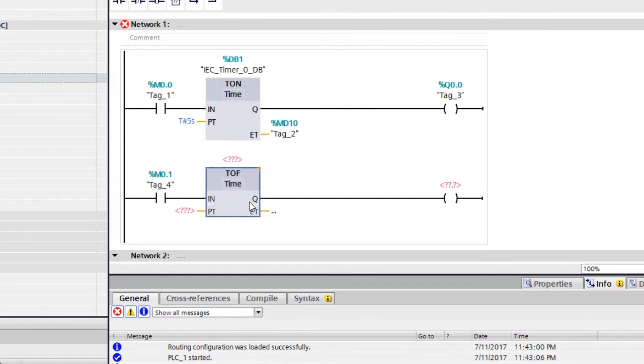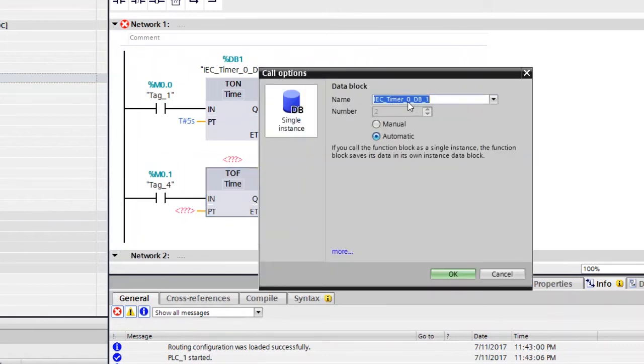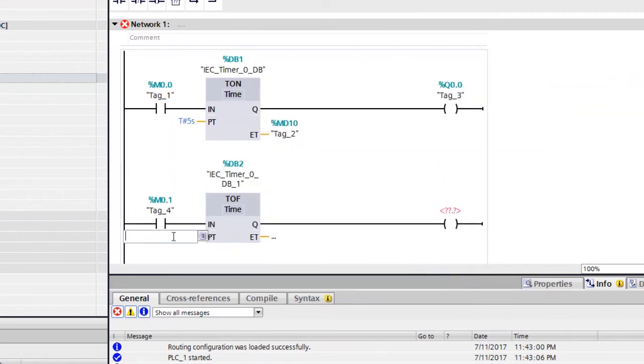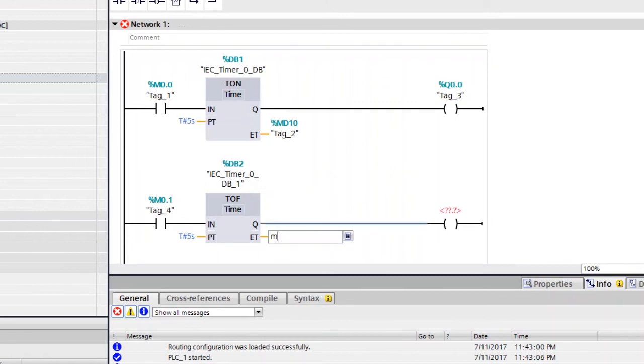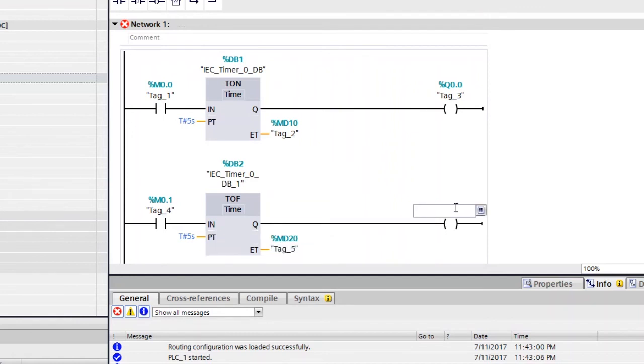Assign address M0.1, then select TOF — T-O-F — and press Enter. In the call options, you can keep the default name or change it; leave it as automatic and click OK. Again, give a preset time — for the off-delay, specify five seconds: type 5 followed by S. For the elapsed time register, use MD20 (since MD10 is already used above). Then assign the output Q0.1 and press Enter.